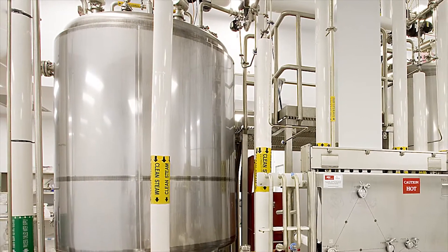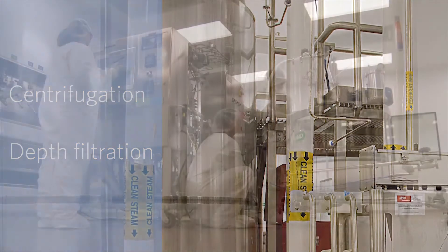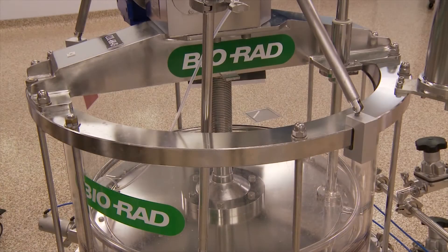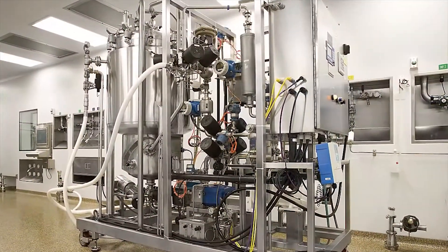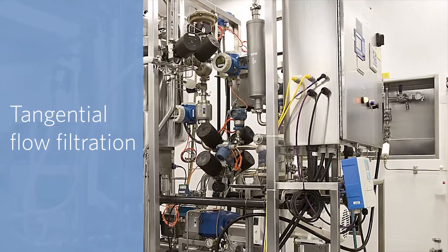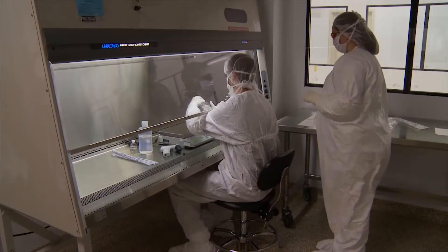The downstream capabilities are highly flexible to accommodate a variety of processes. Primary recovery options include both centrifugation and depth filtration. Chromatography capabilities include columns ranging from 10 centimeters to 80 centimeters in diameter, coupled with chromatography skids covering flow rates ranging from 0.1 to 18 liters per minute. Catalent can also perform viral filtration, tangential flow filtration, and normal flow filtration utilizing single-use cartridges, capsules, and cassettes.